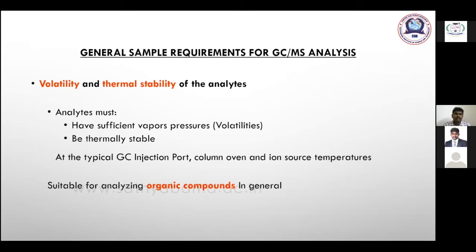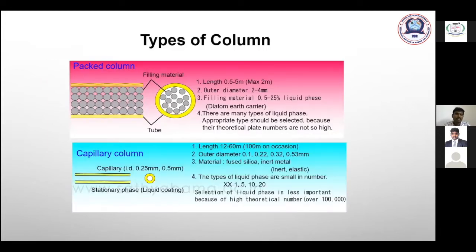General sample requirements for GC-MS analysis: the sample should be volatile and thermally stable. The analyte must have sufficient vapor pressure and thermal stability because in GC-MS the injection port, column, and ion source are all maintained at different temperatures. GC-MS is suitable for analyzing organic compounds. Nowadays everyone uses capillary columns rather than packed columns, with different lengths available, coated with stationary phase liquid having different combinations.